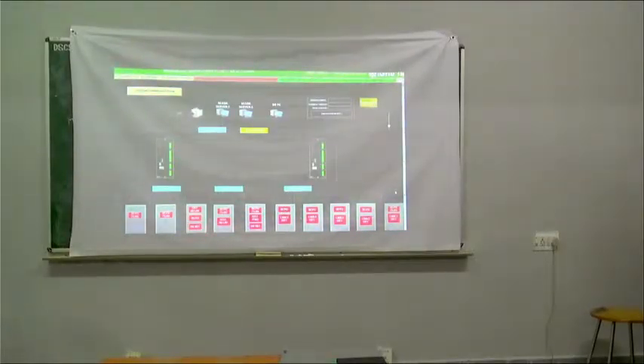So basically this is typically a substation architecture which we discussed earlier. The devices communicate on different protocols through an Ethernet switch. If it is a network protocol like 61850, it will communicate through an Ethernet switch. Otherwise, if it is serial communication, we do it on Modbus. Finally, the data is gathered within the gateway. From the gateway, we are sending it to the control centers, and you have the local SCADA servers for local maintenance and supervision.